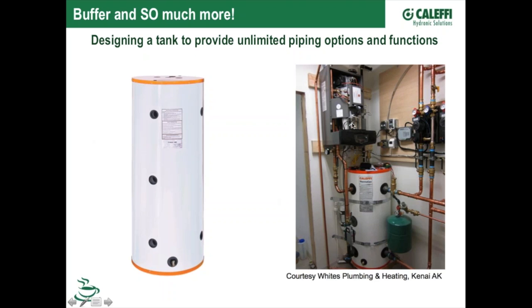He's got a job where he's got a bunch of micro loads in the building, so he's connected his boiler directly to the buffer tank. You can put the sensor from the boiler into the buffer tank now, so the boiler references this as its load. It's going to heat up this tank. You can see he's put a variable speed ECM circulator that ties into the boiler output here, so that pump is going to modulate with the modulation rate of the burner to make sure you're getting just the right amount of flow through that. And now we're going to store that energy in here, and then just off to the right here, we're going to sip off the amount of energy that the load needs.